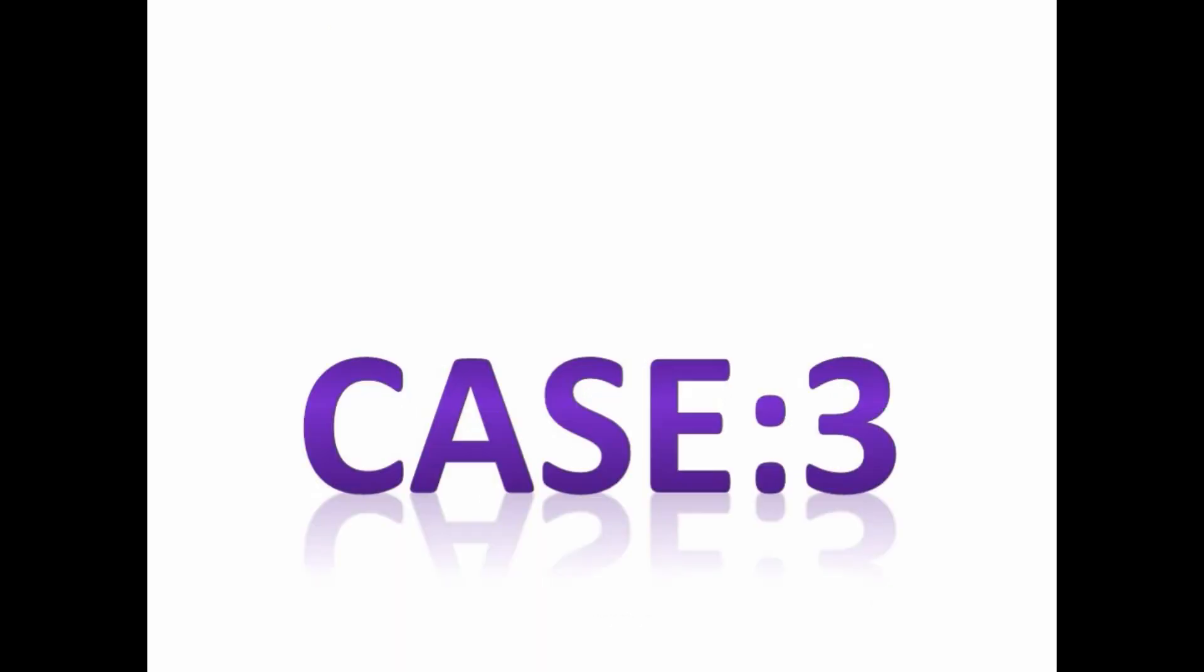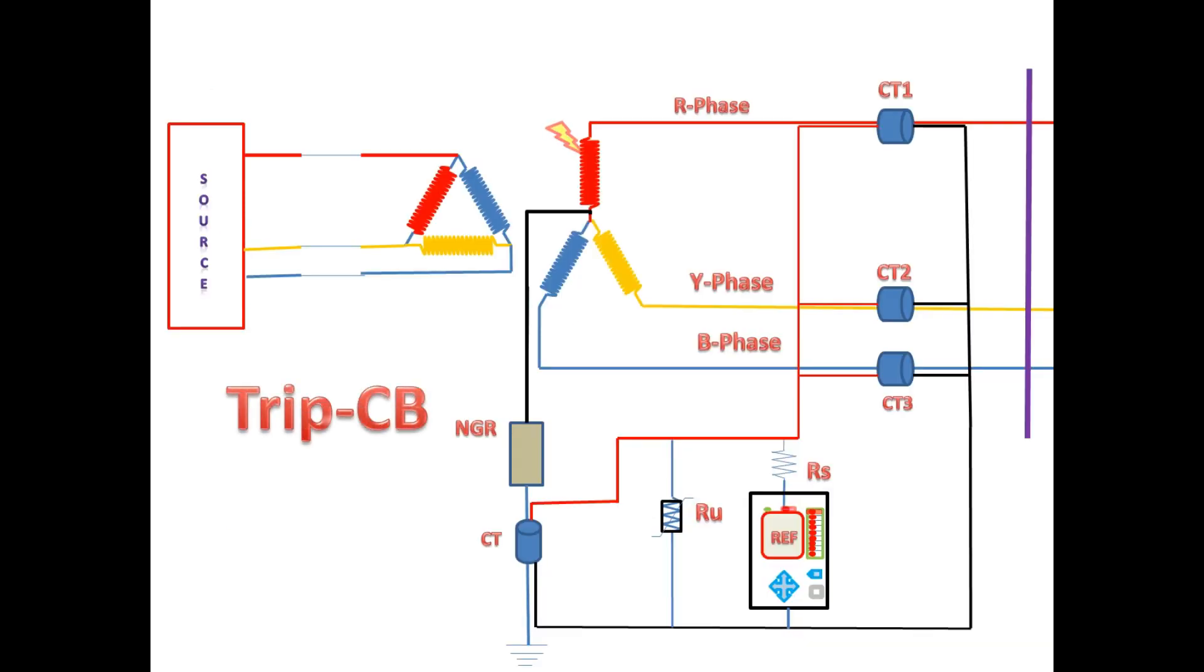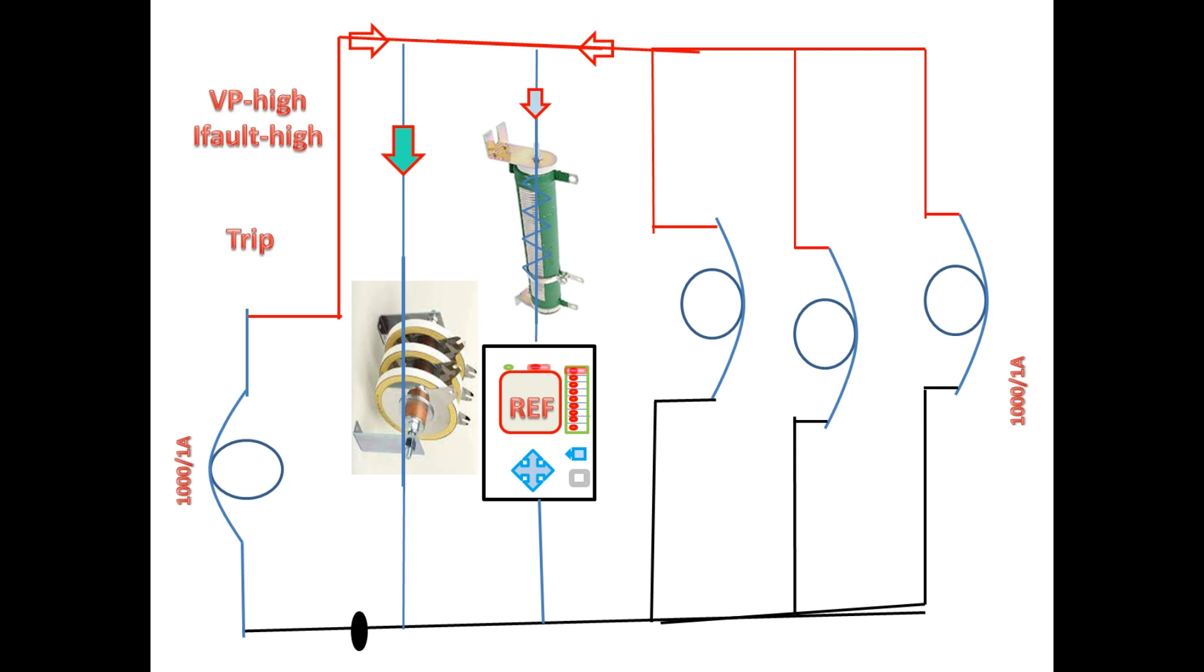In this case we have both resistor. Here also we are going to consider very very high fault. During this time we will have a high peak voltage, i.e. VP. During this time, metrosil resistor will start to conduct current and also the stabilizing resistor will allow the current to relay very very less but sufficient to get pickup on the relay setting. So that only we are finding the RS value with relay setting. Now the relay is also in safer side and device is also protected by giving TRIP by the relay.